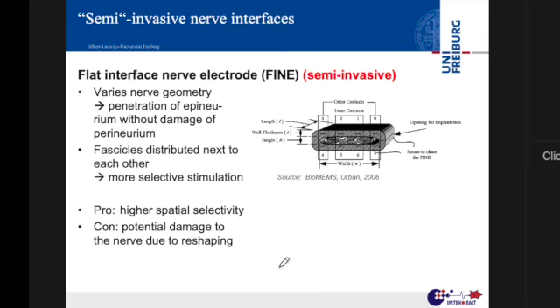Now, with these electrodes, you have, of course, higher neural selectivity, because if you look at the nerve from the cuff electrode, let's say you have 150 fibers here, right? And you have contact 1, 2, 3, and number 4. So that's the cuff electrode, which is semi-selective, because if you stimulate here, the electrical field will be something like this for each contact. So that's the axon group you're activating. If you use the intraneural electrode, you will have this small PCB with single contacts. And since it's inside and the outside of the nerve is isolating, you can actually apply smaller current. So what you see is that you will activate smaller axon groups and smaller fiber groups. So the chance that you will activate single sensations on your hand gets bigger with the increase in contacts. So that's really important here.